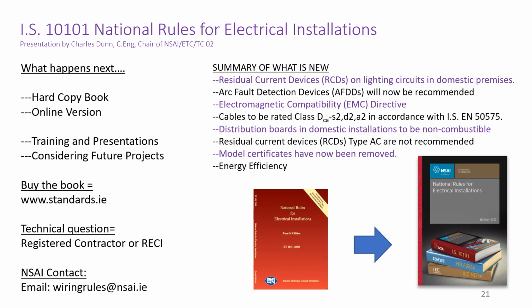To finish off this presentation, here is a quick summary of what's new in IS 10101. Residual current devices, RCDs, on lighting circuits in domestic premises. Arc fault detection devices, AFDDs, will now be recommended. Electromagnetic compatibility, EMC directive. Cables to be rated class Dca, s2, d2, a2 in accordance with EN 50575. Distribution boards in domestic installations to be non-combustible. Residual current devices, RCDs, type AC, are not recommended. Model certificates have now been removed. Energy efficiency.